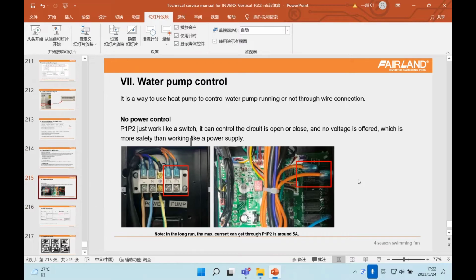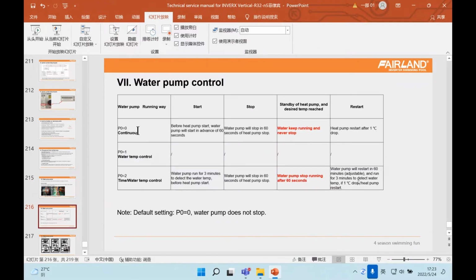And finally, the water pump control, which we call heating priority in the markets. When our heat pump runs, it always needs the water pump to run and provide the water flow volume. So we have a connection between the water pump and the heat pump through terminals P1 and P2. It is a dry contact, normally open with no voltage, just a connection like a bridge. After the connection, the water pump will run with the heat pump. Normally we set the water pump to always run for the heat pump, to support it with sufficient water flow volume.